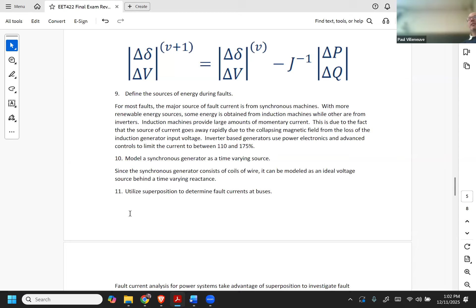And that first little bit is when we have really high currents because we have a fair amount of asymmetrical current. And so those typically are our withstand capabilities of our breaker. So not interrupting, but withstand. So the first few cycles after a fault, our breakers, it's not fast enough to operate, but they got to be able to withstand the amount of current that they see. And then after 2 to 3 cycles, now the breaker might be expected or probably is expected to interrupt, isolate. And so it has to be able to interrupt. So you have breakers with interrupt and withstand ratings.